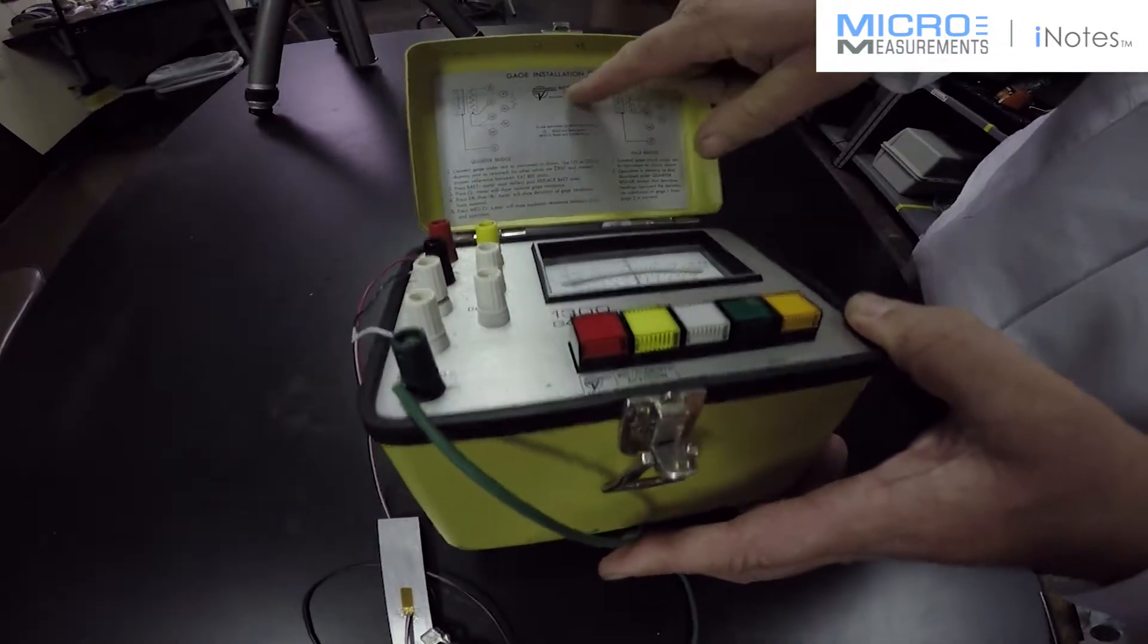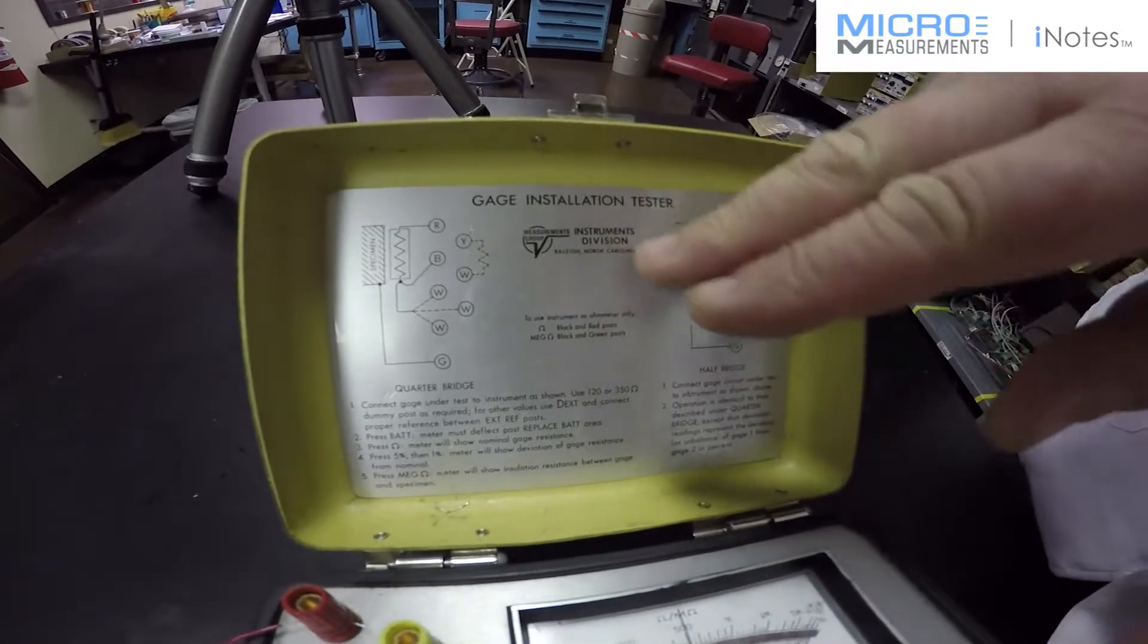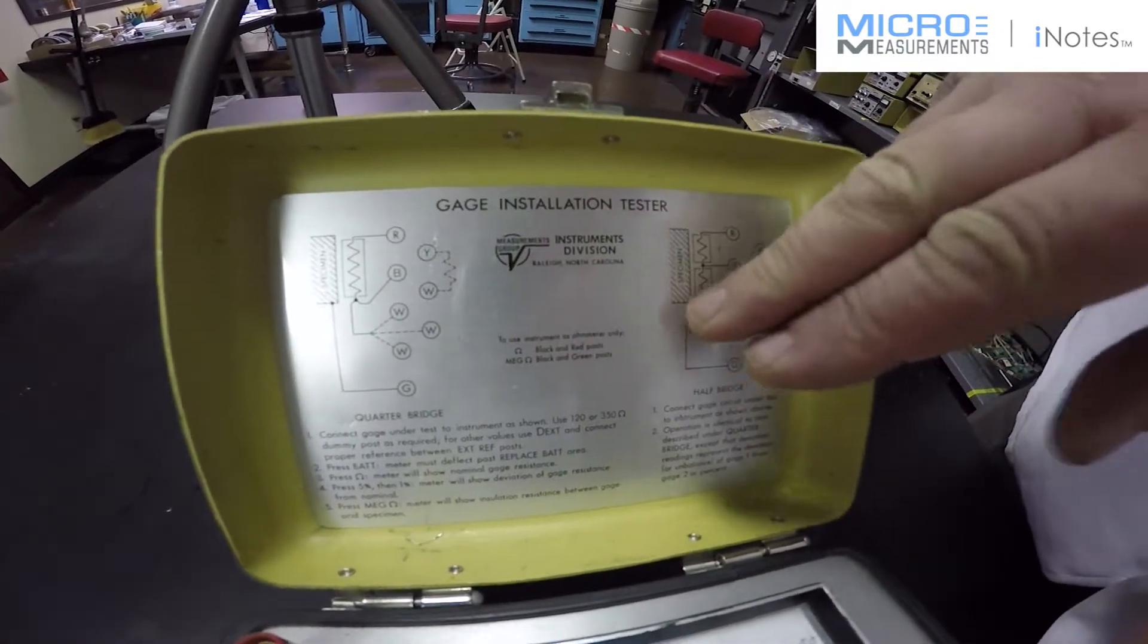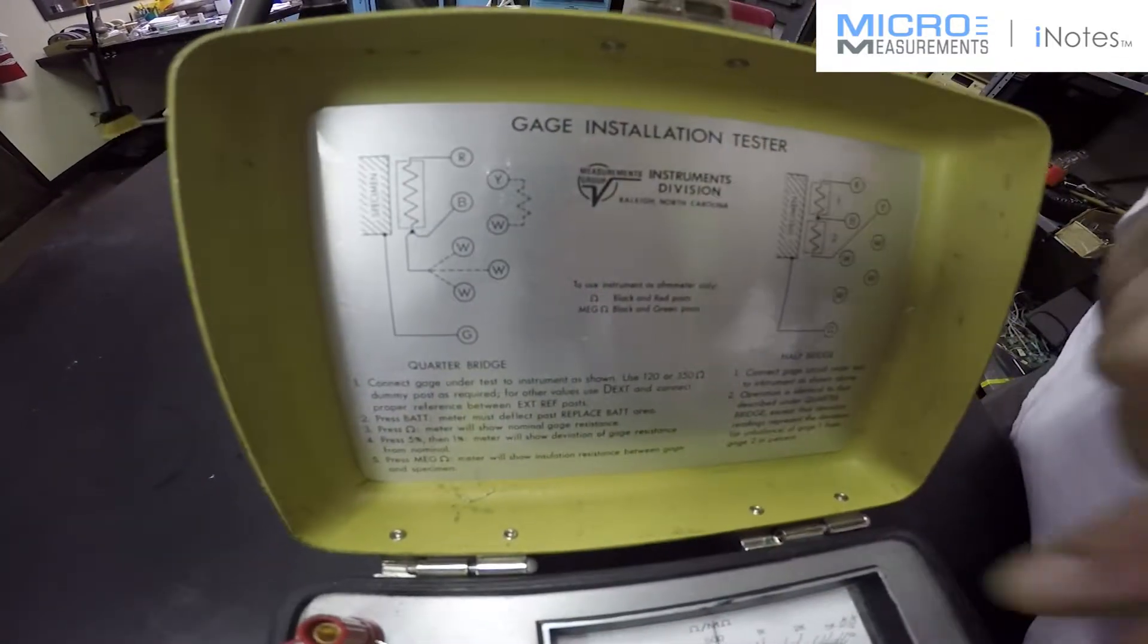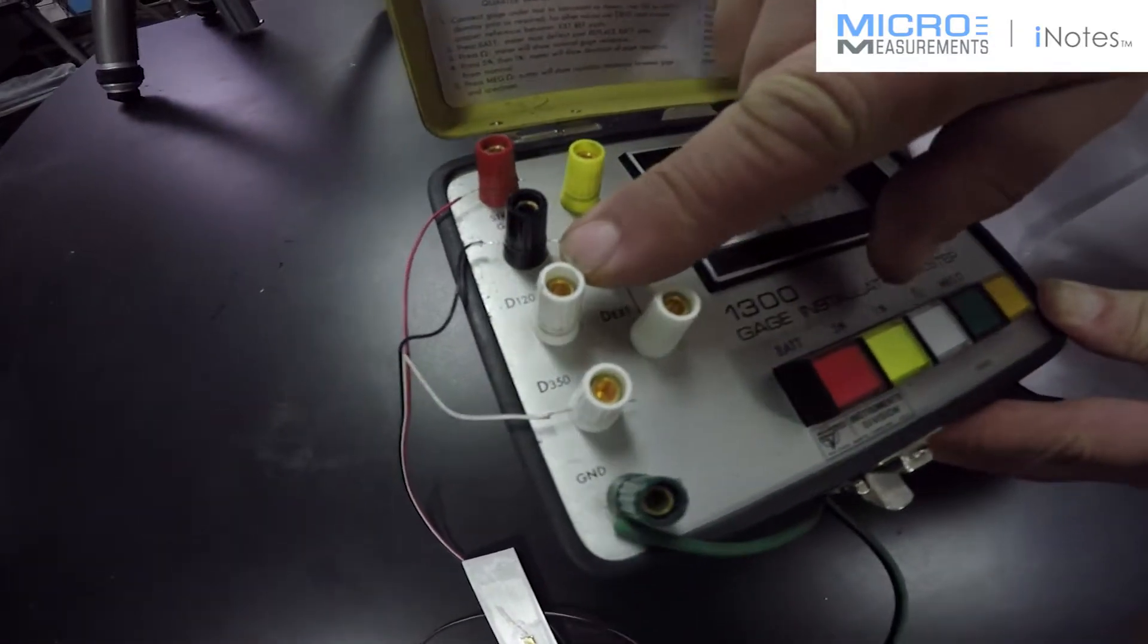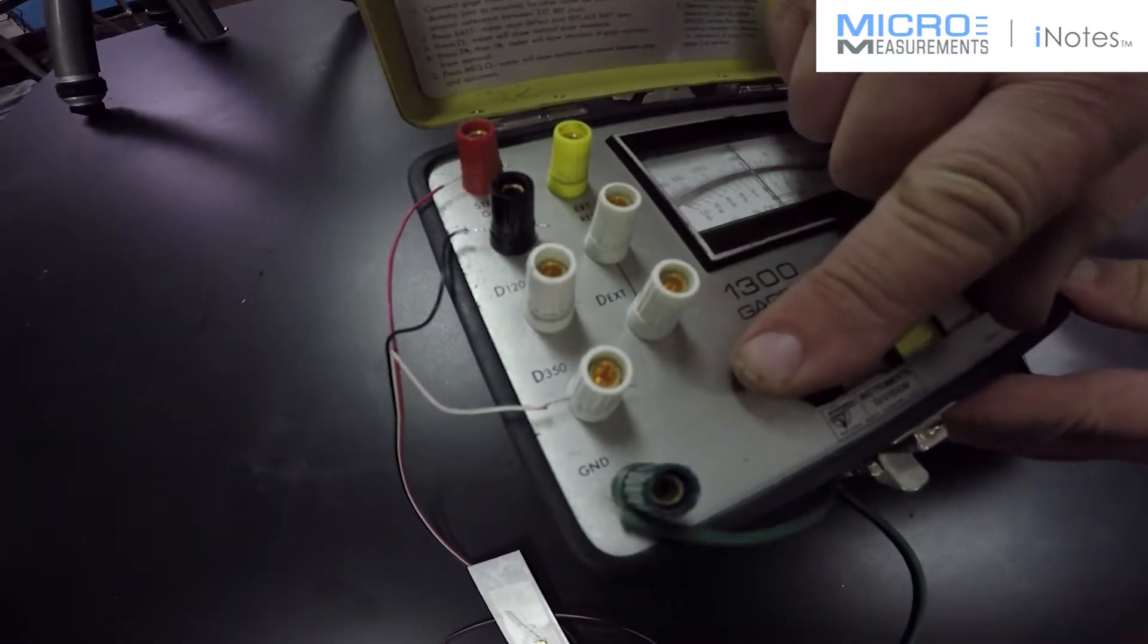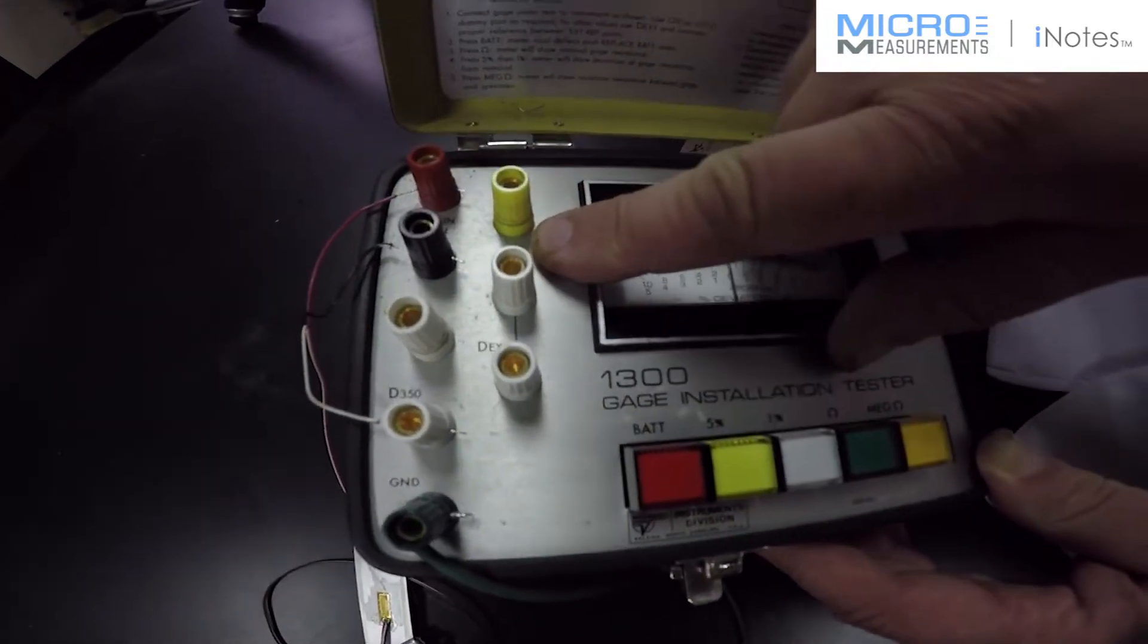This instrument works with just about every strain gauge possibility. You can connect to it half bridges, full bridges, quarter bridges, and really any resistance. It has built in here dummy resistors for connecting a 120 or 350 ohm bridge. If your gauge is 1000 or any other resistance, you can hook up an external reference.